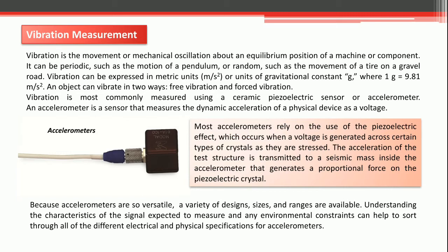Measurement of vibration may be made with a transducer sensitive to amplitude, that means displacement, velocity or acceleration. The output of this transducer, after necessary signal conditioning, is fed to the display unit, indicating the original measured variable, or another variable is derived from it through integration or differentiation. Vibration measurement is complex because of its many components like displacement, velocity, acceleration and frequencies. Each component can also be measured in different ways, like peak to peak, peak, average, RMS.